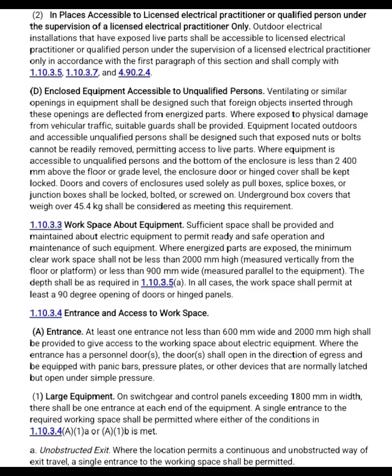1. Large equipment. On switchgear and control panels exceeding 1800 mm in width, there shall be one entrance at each end of the equipment. A single entrance to the required working space shall be permitted where either of the conditions in 1.10.3.4(A)(1)a or (A)(1)b is met. A. Unobstructed exit. Where the location permits a continuous, unobstructed way of exit travel, a single entrance to the working space shall be permitted.